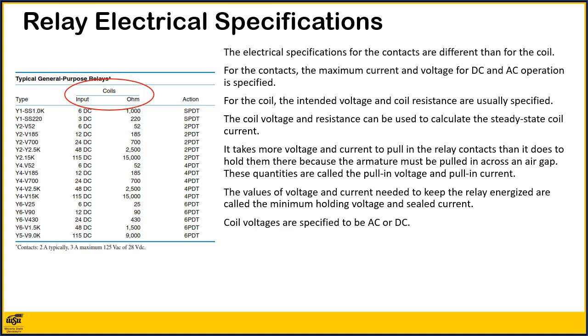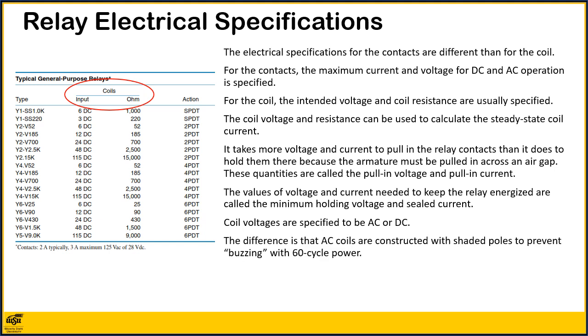Coil voltages are specified to be either AC or DC. The difference is that the AC coils are constructed with shaded poles to prevent buzzing with 60 Hz power. The shaded pole relay has a metal ring around the pole face of the electromagnet. Magnetic flux induced in this ring keeps the relay closed when the AC cycle goes through 0 volts.